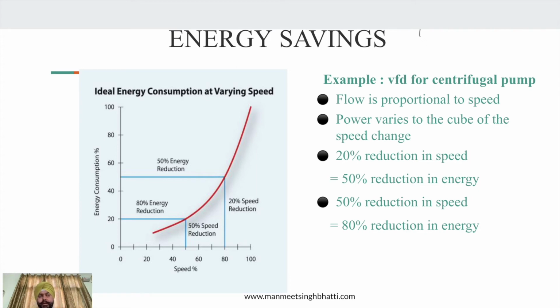But still, whenever we are sizing a motor, the motor is sized almost 20 to 30% higher than the mechanical load, just in case there are higher loads or some kind of design problem. So your motors are already 20% higher than the actual load. That is the basic design philosophy we follow across the globe.